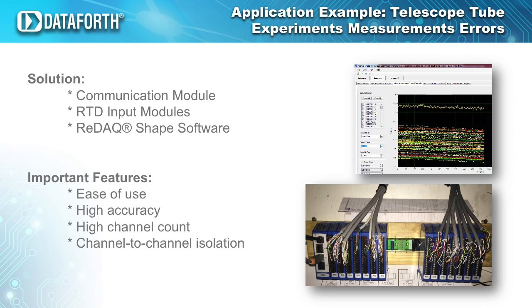Each sensor, using a 30-foot or 10-meter wire across the ground, was connected to one of 14 MAQ20 RTD31 input modules. Despite the low-level signals coming from the sensors, MAQ20 was still able to achieve 0.08% measurement accuracy. Additionally, important factors included lead wire compensation, rejection of noise, and maintaining channel-to-channel isolation to minimize crosstalk in this high channel count application. The MAQ20 COM4 module was used to transfer the collected temperature data to a host computer, which runs data acquisition software called ReDAQ Shape.